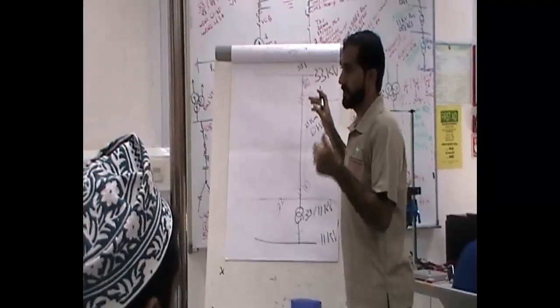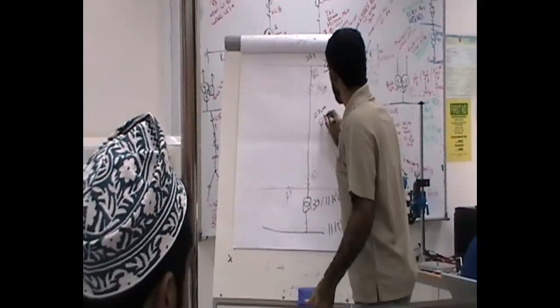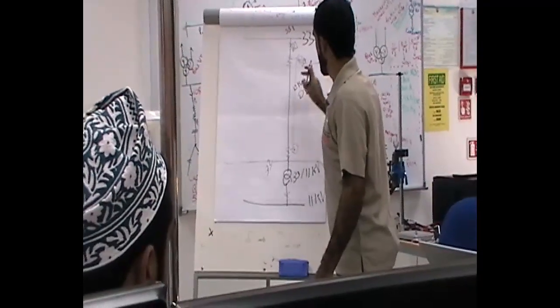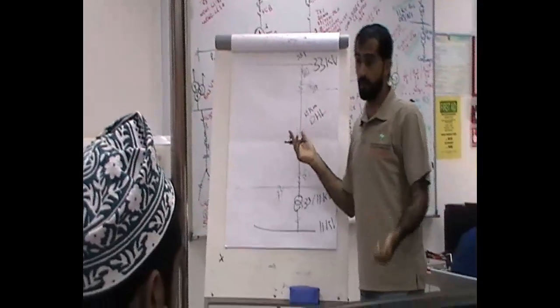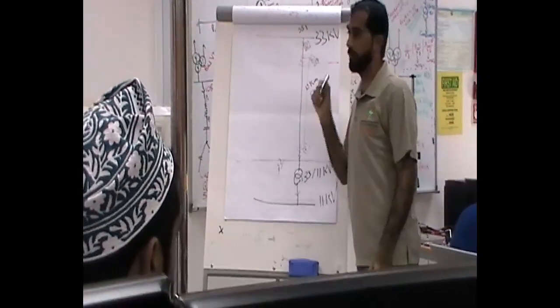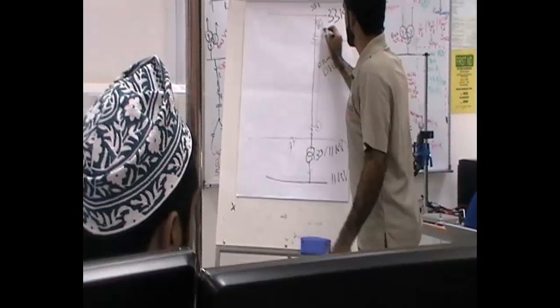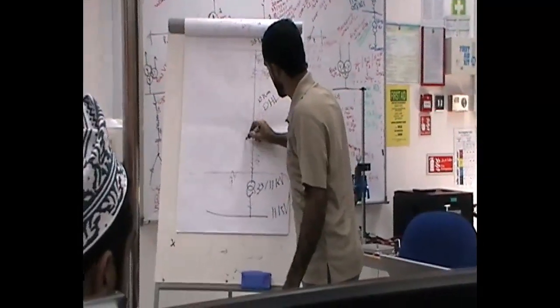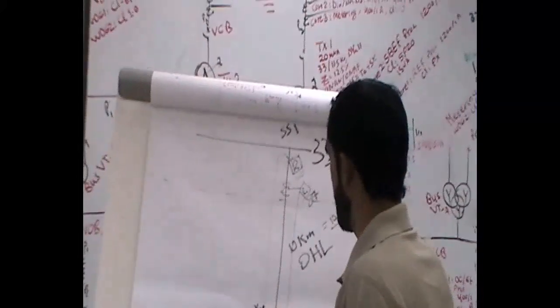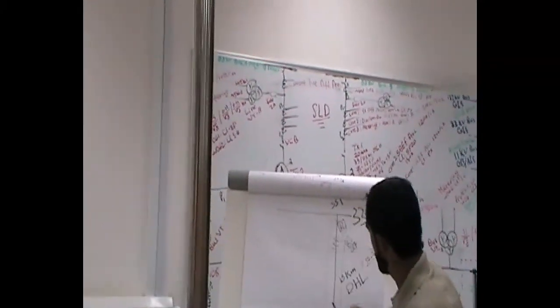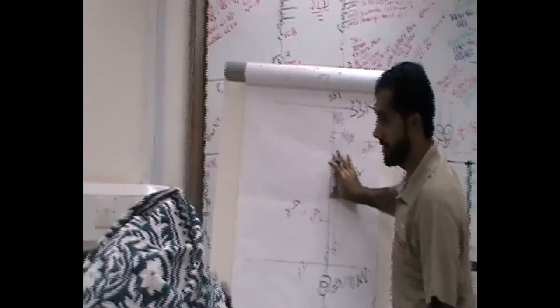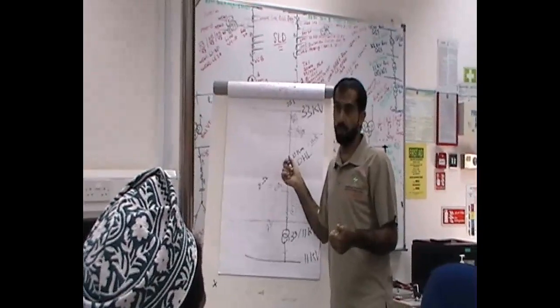So, now assuming we have a distance relay. The setting of distance relay is in ohms. I have 10 kilometer. Can I calculate the impedance of the line? I have the data of the overhead line, so I could calculate the impedance of the line. I will enable distance relay here. And zone 1 is only reaching up to 80% of the line. Assuming the line is like 10 ohm, 80%, the setting of zone 1 should go like 8 ohm. Whenever there is fault inside this zone, definitely it will be in the line. So my timing here is 0 millisecond.